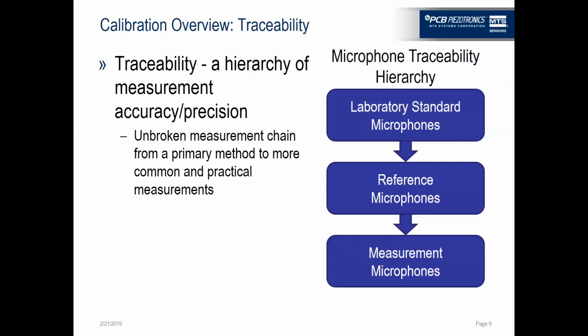And in order to do that, we have to have a way of tracing our measurement back to some standard, something that says this is the conversion from a Pascal to a volt. And in many cases, what we use is a chain, a traceability chain, where we'll generate a reference via primary calibration with a laboratory standard microphone. From there, we will do comparison calibrations from the laboratory standard to reference microphones to the measurement microphone that you'll use in the field.